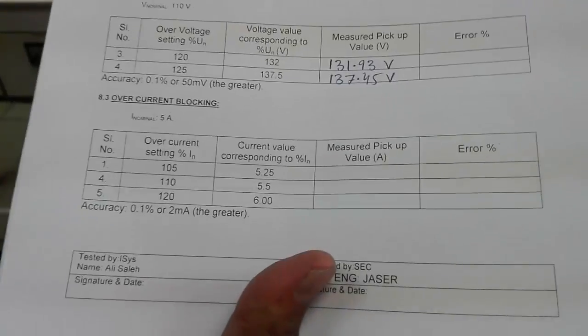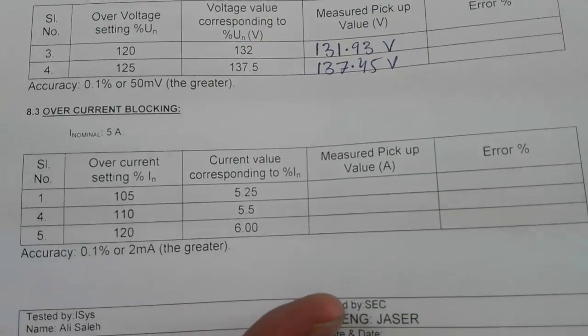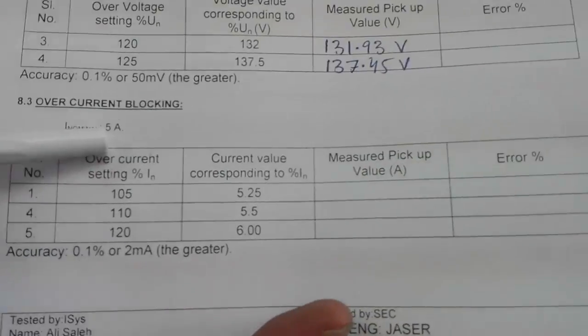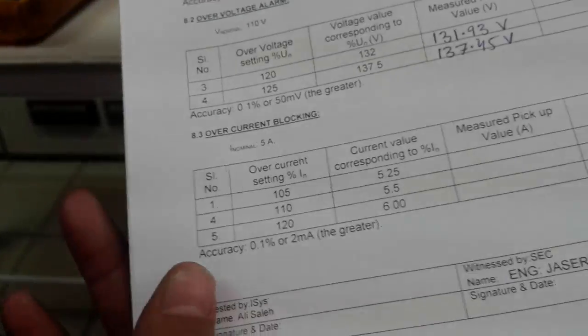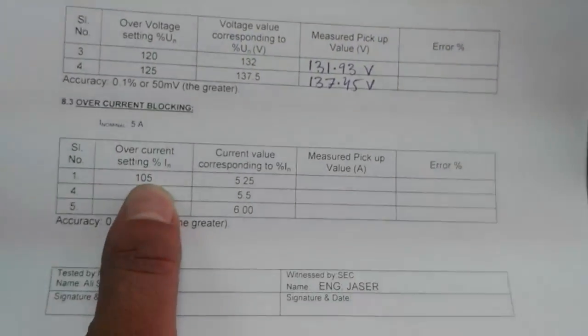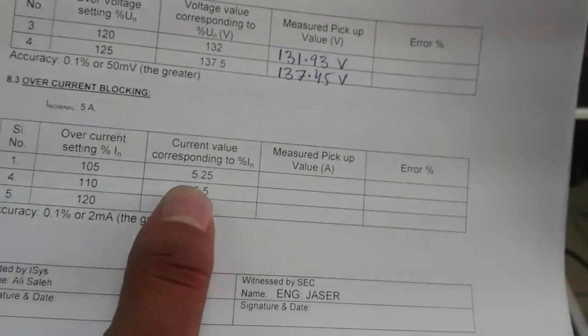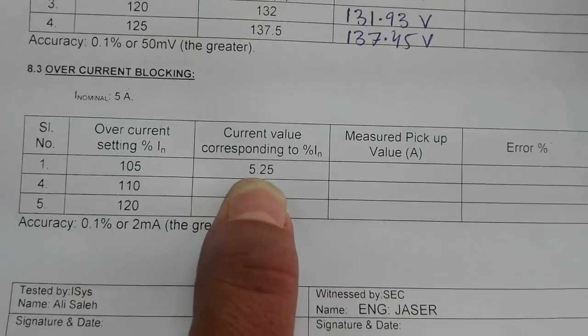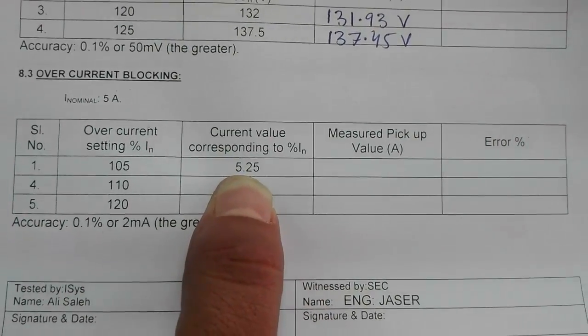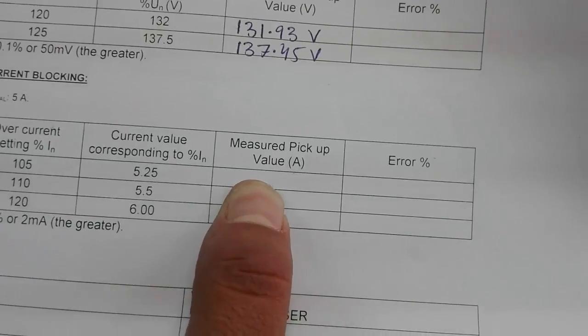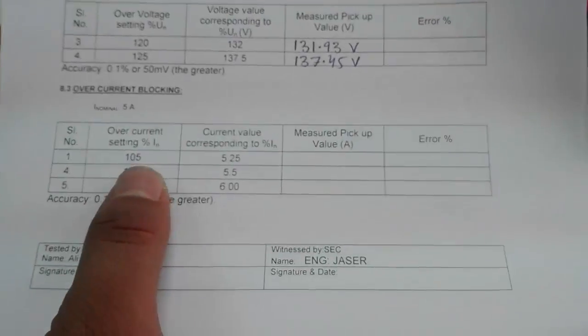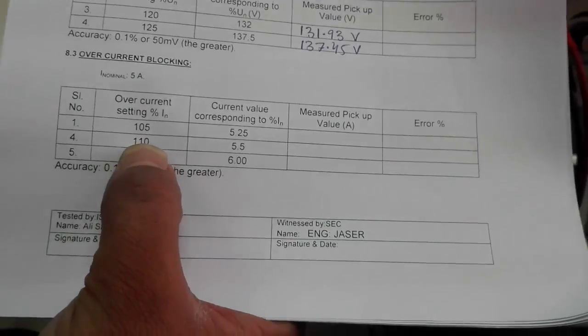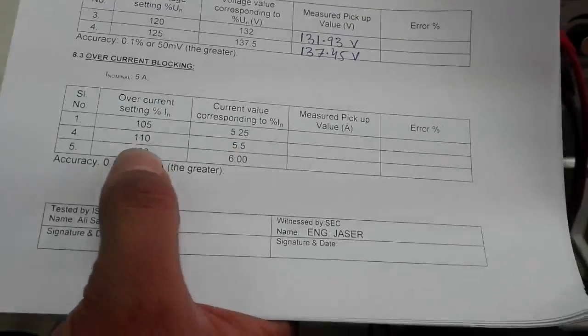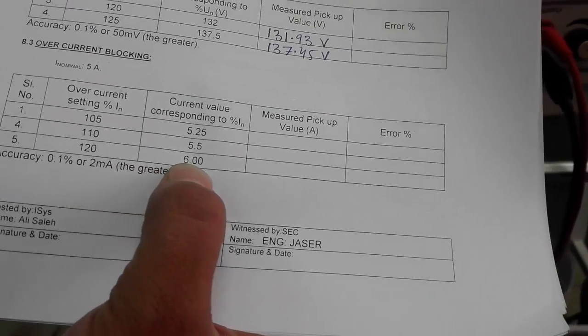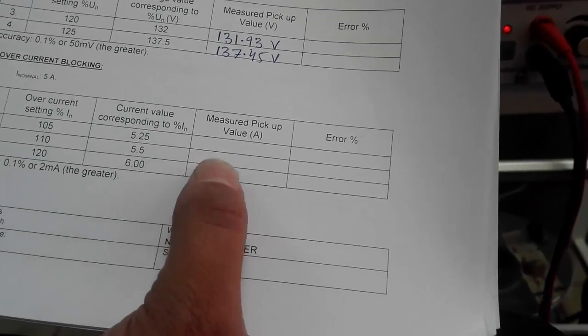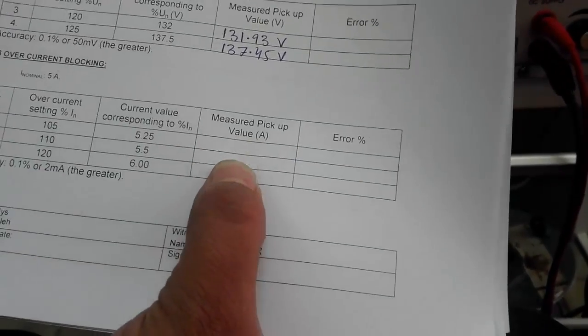Now the next test which we will perform is for over current blocking. For this the nominal current is 5 ampere, so we will slowly and gradually increase the current. First we will inject by 105%, that makes it 5.25, and we will measure the pickup value. Then we will increase by 110%, that makes it 5.5 amps, then 120%, that makes it 6 amperes, and similarly we will measure the pickup value for these three.